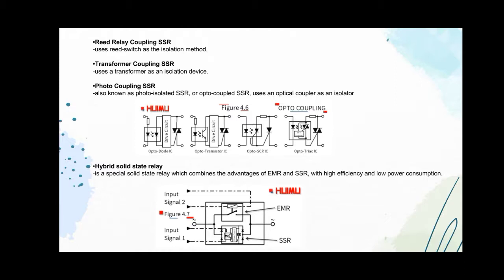So when input signal 1 is applied, the SSR immediately switches to the on state. Since the electronic switch has no moving parts, it can switch the load stably and quickly and does not generate an arc due to high line voltage or heavy surge current during switching. After the load current is generated, the EMR will be controlled by control signal 2 and switched on. Because the EMR is connected in parallel with the SSR, the output contact of the EMR is energized without voltage and there is no arc across the contacts. Then after a certain delay, the contact bouncing of the EMR settles down and the SSR will be turned off. The EMR works also with no heat, so the hybrid SSR can be run without a heat sink installed.